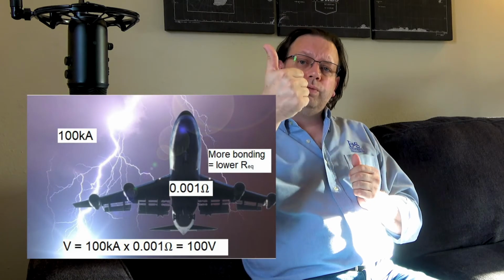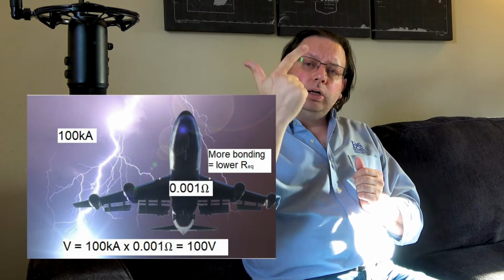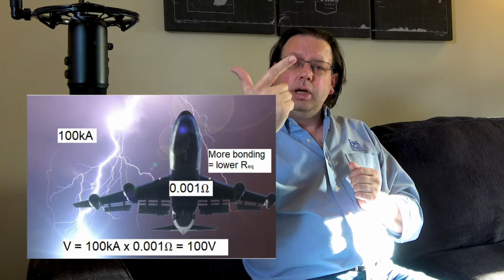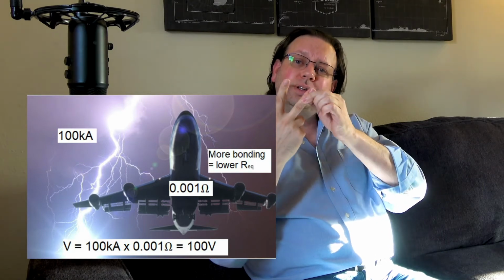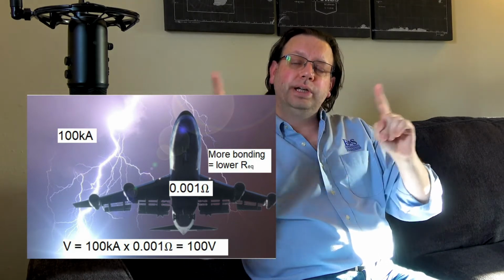When we're designing our grounding systems, we rarely can control the voltage we're going to see. We can rarely control the current we're going to see, but we can control the resistance, or the difference in resistance, between any two given points. So when you're designing a grounding system, you should think about being able to lift that system into space, and it should still function properly in most cases. And the exceptions could be certain fault clearing conditions if you're dealing with utility level antenna systems, or certain electronic systems such as MRI machines, etc.